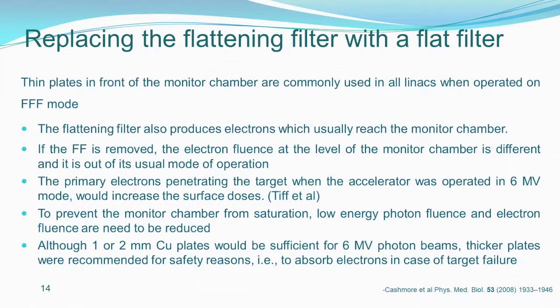The primary electrons penetrating the target when the accelerator was operated at 6 MV mode, for example, would increase the surface dose. So having a thin plate would reduce these primary electrons reaching the patient and increasing the surface dose, and prevent the monitor chamber from saturation. See, the low energy photons and electrons, when you don't have a flattening filter, would make your monitor chamber almost saturate its value. So to avoid that, they keep this thin filter. So that is another help of having a filter there.